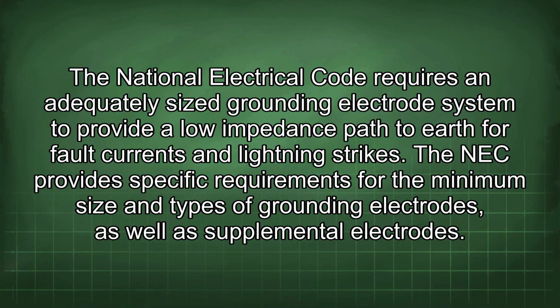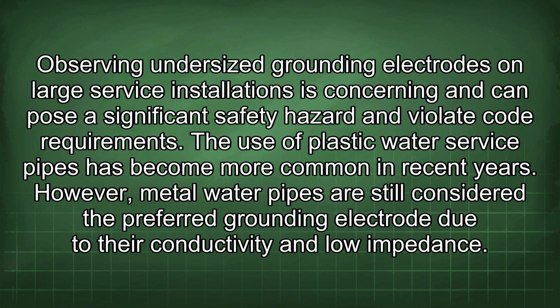The National Electrical Code requires an adequately sized grounding electrode system to provide a low impedance path to earth for fault currents and lightning strikes. The NEC provides specific requirements for the minimum size and types of grounding electrodes, as well as supplemental electrodes. Observing undersized grounding electrodes on large service installations is concerning and can pose a significant safety hazard and violate code requirements. The use of plastic water service pipes has become more common in recent years.